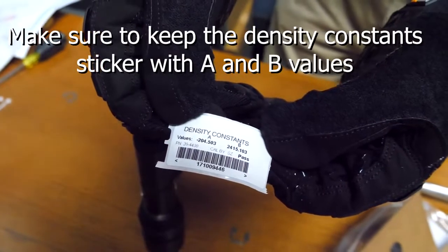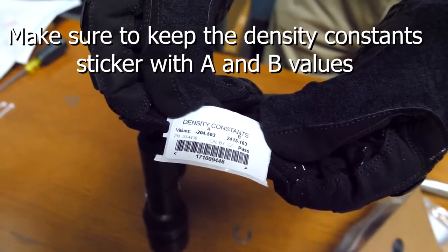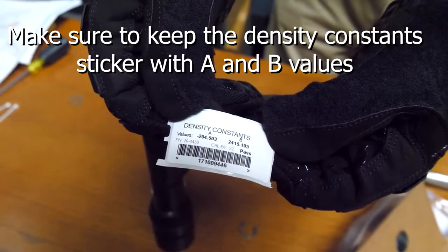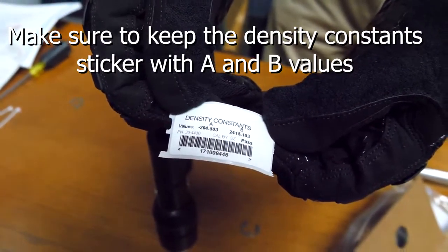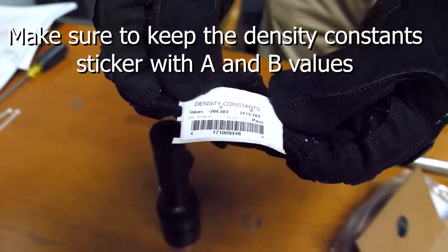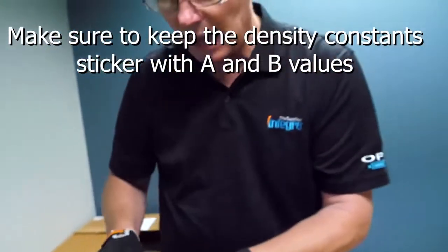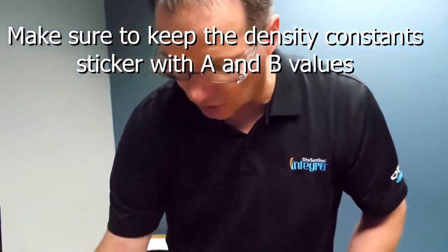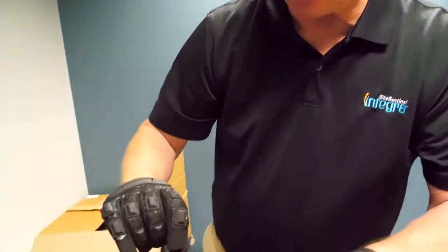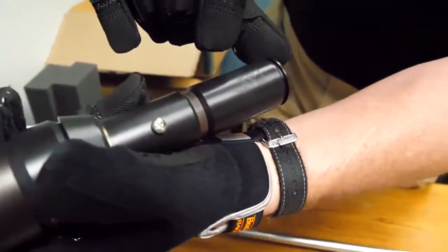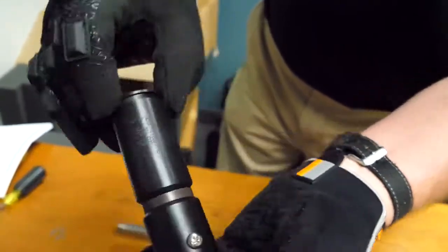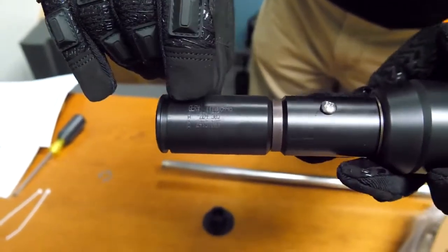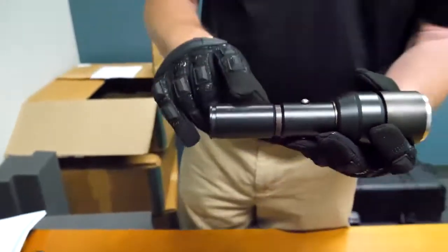Those numbers, the values A and B, have to be programmed into the Integra or Nano tank gauge in order for the sensor to work properly. So you want to hang on to this. If by some chance you lose that, the numbers are also printed and stamped on the float itself, and they seem to hold up pretty well. I've pulled these out after being installed for several months and could still read those numbers.